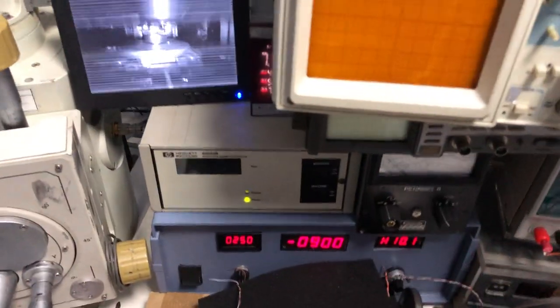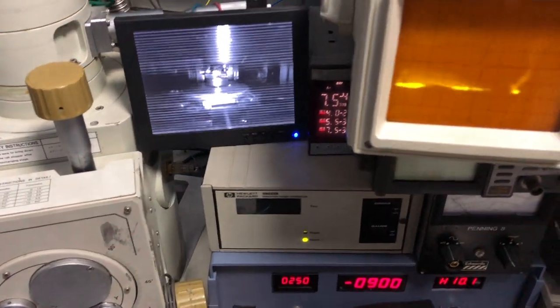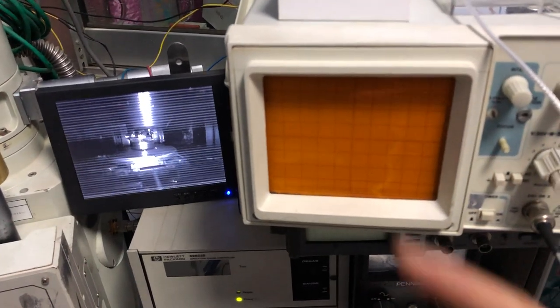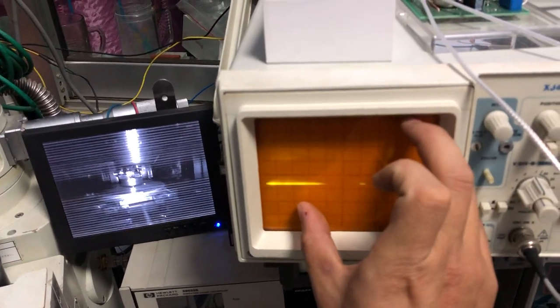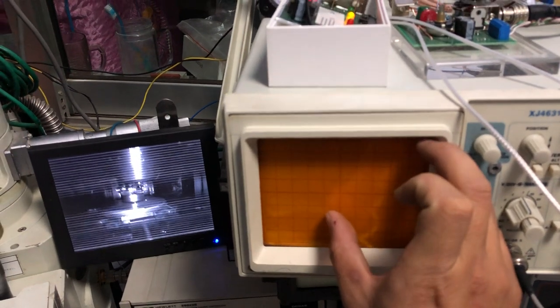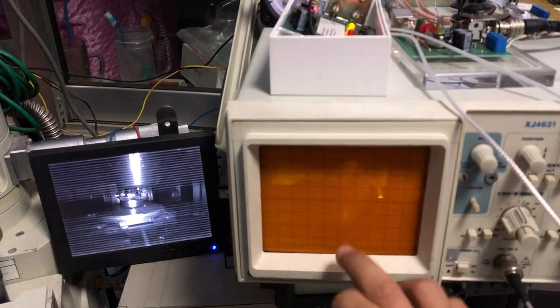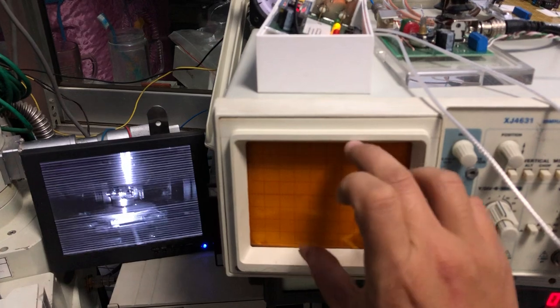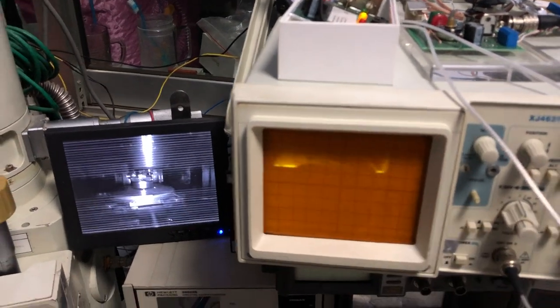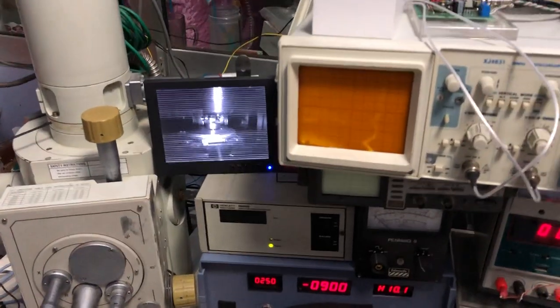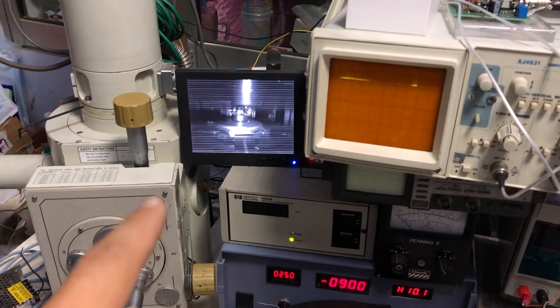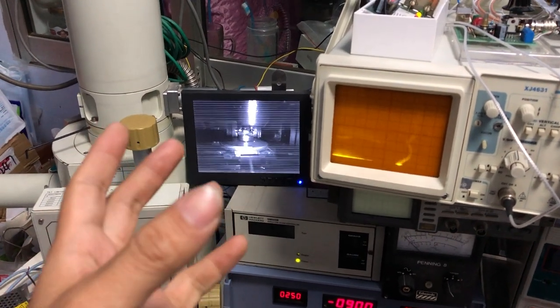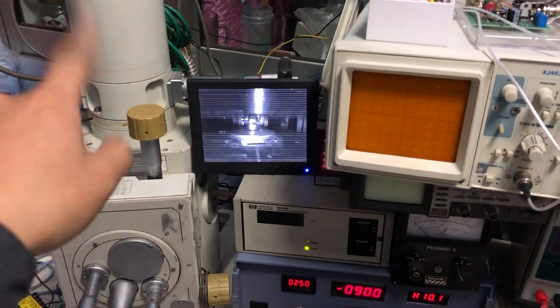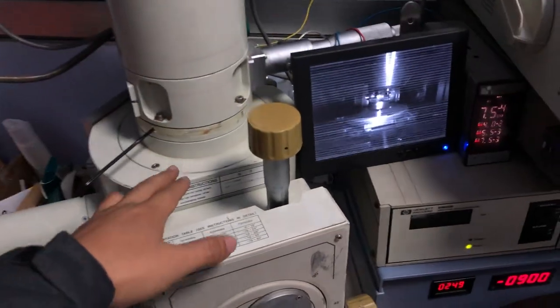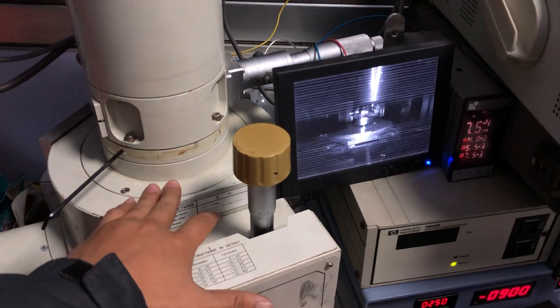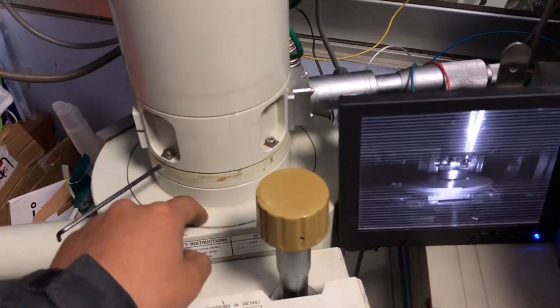So when I see the picture and adjust the focus, the image is moving back and forth, in this direction, this direction. So I think maybe I got the column not aligned with this structure inside the sample chamber.